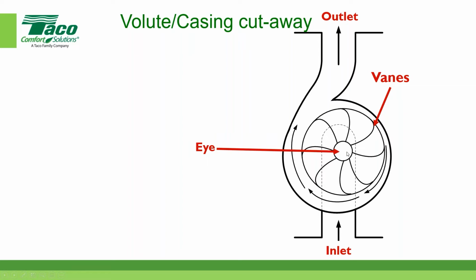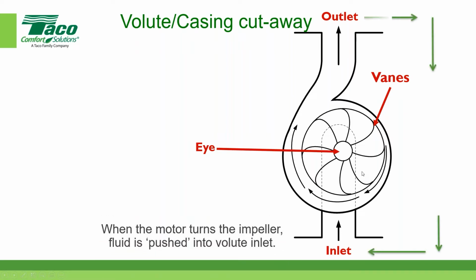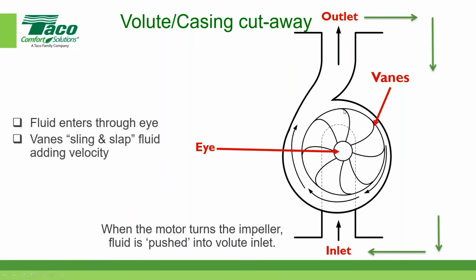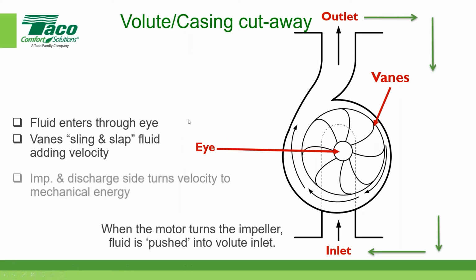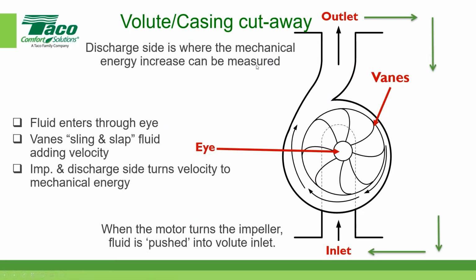It comes up through and in the eye, and then notice the direction of these arrows. It gets slung and/or slapped to create this flow. A lot of people think it's actually scooping, but if you look at the way the impeller's designed and the direction of these arrows, it's slinging or slapping the water, and that's how it adds. As it gets up into this area here, that's how it adds that velocity and creates the mechanical energy that we talked about. Okay, that mechanical energy can be measured.